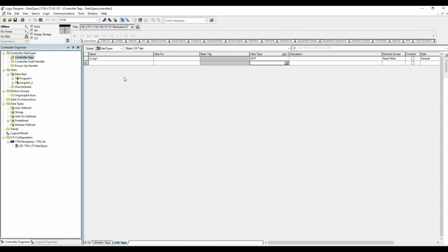So now that we saw how the int data type works, in later firmwares, I believe firmware 24 and above, Rockwell introduced a new fundamental data type. They call it long integer, and essentially instead of 32 bits, it's 64.